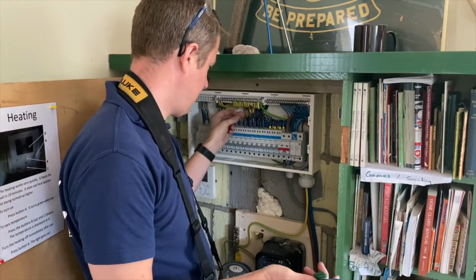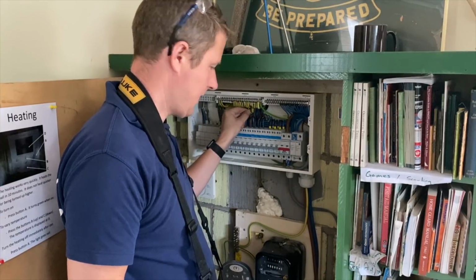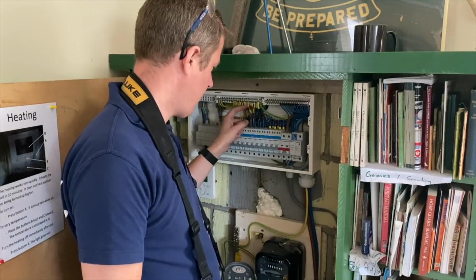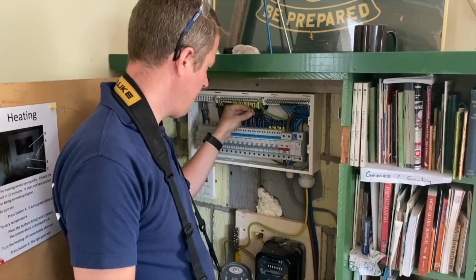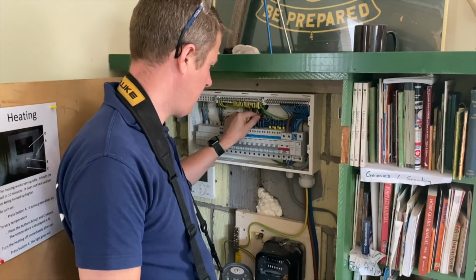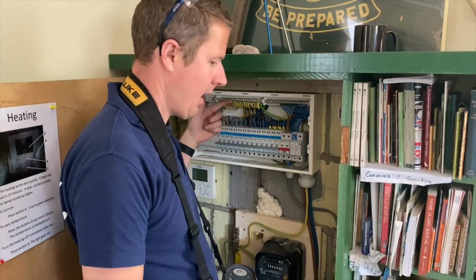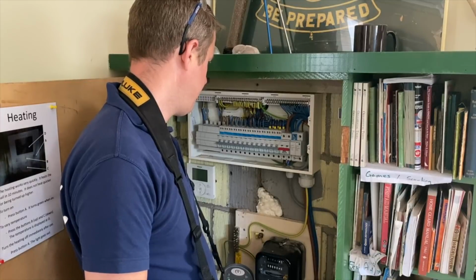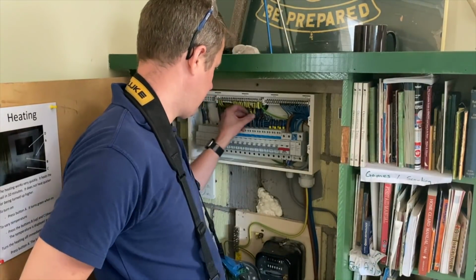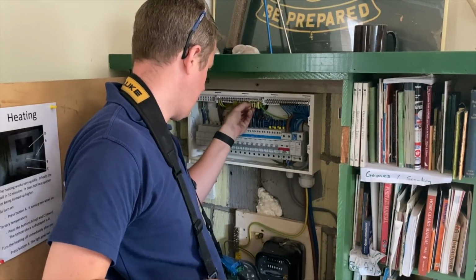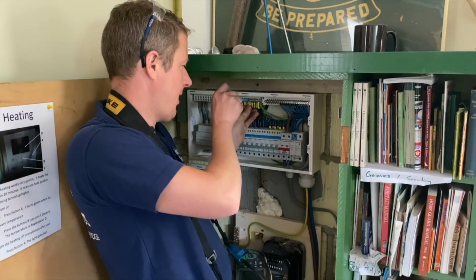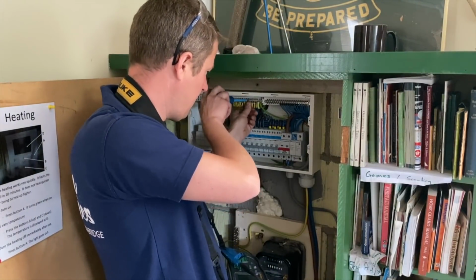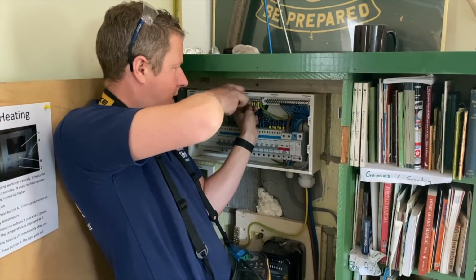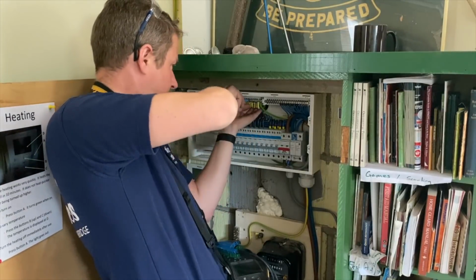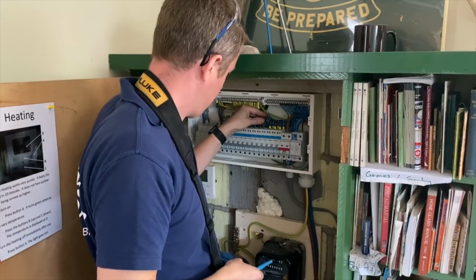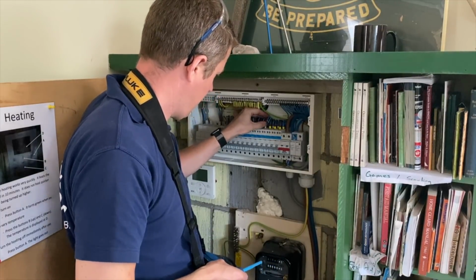Now there's another test that we need to do as well with the ring final circuit, which is to check that there aren't any interconnections. For that one, it's usually on new builds, we connect one leg of the live to one leg of the CPC, and the same with the other, and then we test R1 and R2 at the socket outlet. I'm not going to do that in this case because I don't think it's really necessary, and it's going to ruin my bend radiuses on my cables. But just so you know, there is another sort of ring test that is not on the certificate, but it's down there as an option, and a lot of people recommend that you do it. So now I can neatly put my cables back in.